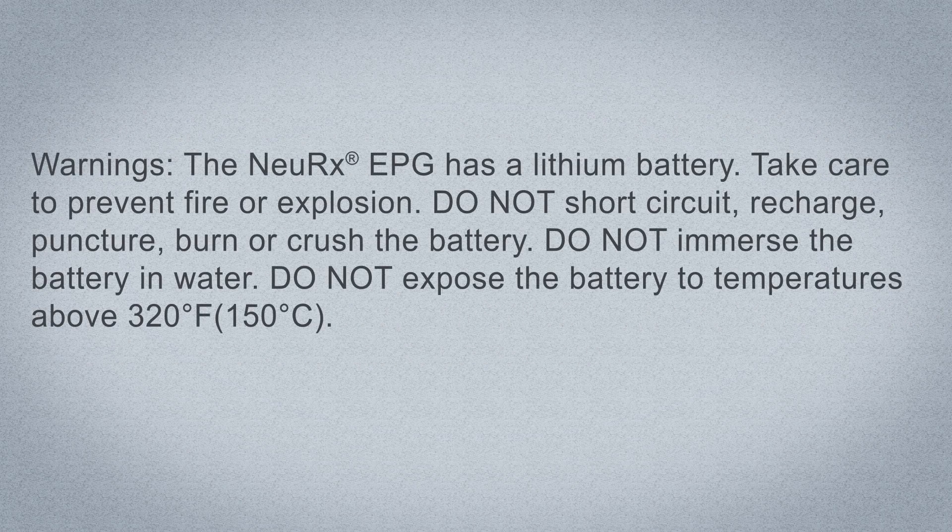The NeuRx EPG has a lithium battery. Take care to prevent fire or explosion. Do not short circuit, recharge, puncture, burn, or crush the battery. Do not immerse the battery in water. Do not expose the battery to temperatures above 320 degrees Fahrenheit or 150 degrees Celsius.